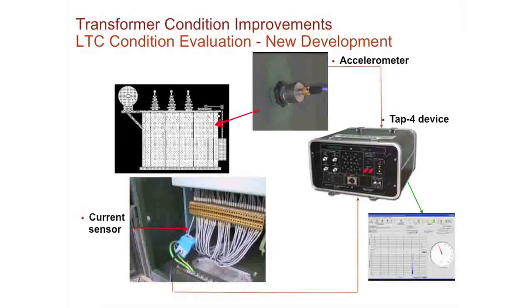LTC condition evaluation, some of the new developments we have going on. We have the accelerometers, we have a TAP 4 device, current sensing device. All these component parts and monitoring devices tell us more information about the LTC than we had previously. What it allows us to do is somewhat determine the maintenance cycles on an LTC.